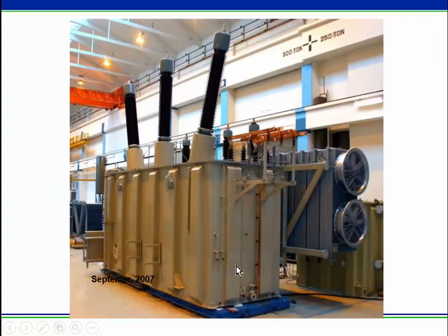Here's a more moderately sized power transformer. Notice the fans on the cooling fins. These work on a principle of natural convection, so the oil inside the transformer naturally circulates through the radiators, and then for a little extra cooling you can turn the fans on across the radiators. So oil level becomes important. If oil level gets too low, then you lose the flow through the radiators.